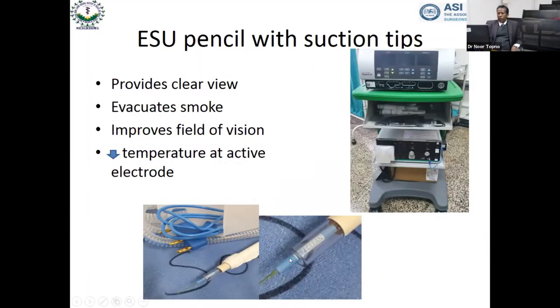Now, another new innovation which has recently come up is how to evacuate the smoke. So here, you can make out there is a hollow channel here. Through this, whatever smoke comes out gets evacuated. And in the machine, this is the unit which actually has a bacterial and also a particulate filter through which it goes. What it does effectively is, apart from creating a safe environment for the surgeon, it also reduces the temperature by taking away the hot gases which come out.